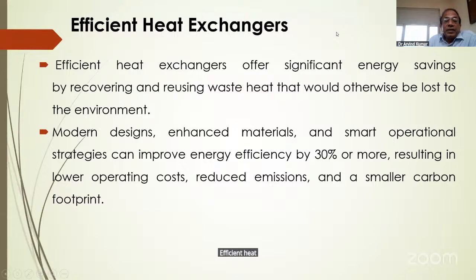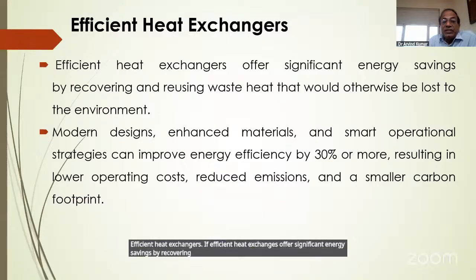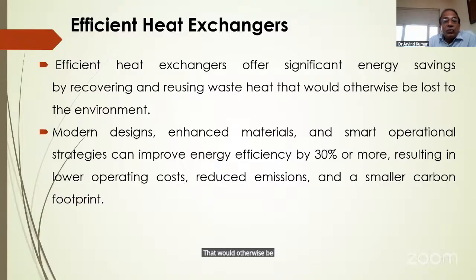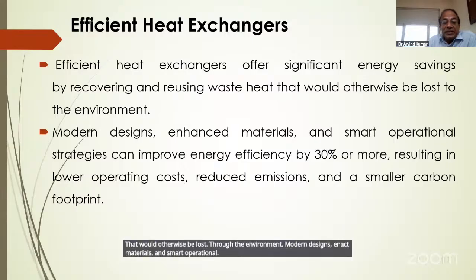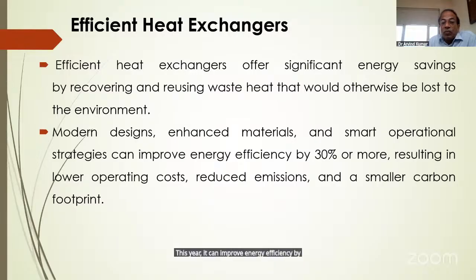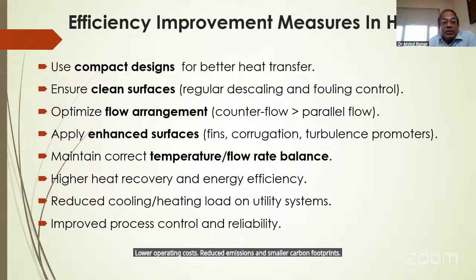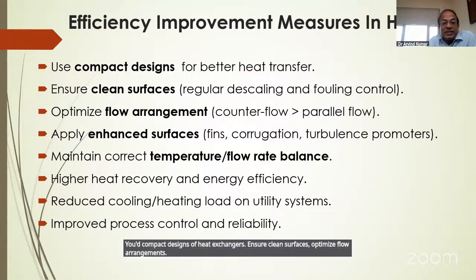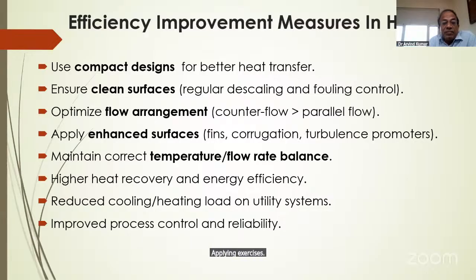Efficient heat exchangers offer significant energy savings by recovering and reusing waste heat that would otherwise be lost to the environment. Modern designs, enhanced materials, and smart operational strategies can improve energy efficiency by 30% or more, resulting in lower operating costs, reduced emissions, and smaller carbon footprints. Use compact designs of heat exchangers, ensure clean surfaces, optimize flow arrangements, apply enhanced surfaces, and maintain correct temperature for high heat recovery and energy efficiency.